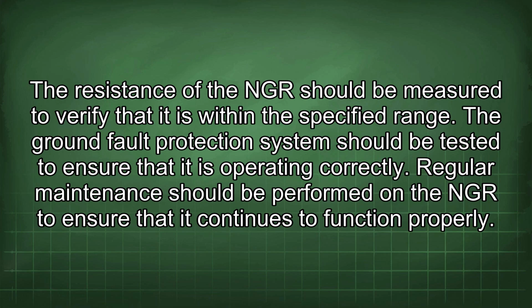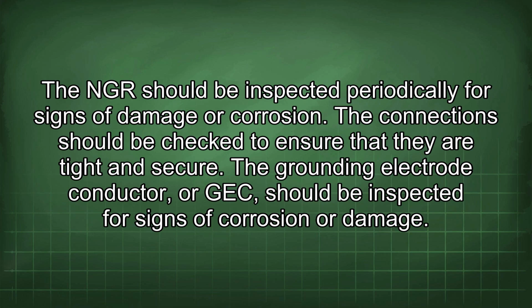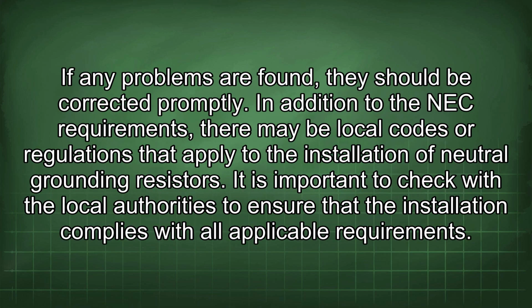Regular maintenance should be performed on the NGR to ensure that it continues to function properly. The NGR should be inspected periodically for signs of damage or corrosion. The connections should be checked to ensure that they are tight and secure. The grounding electrode conductor, or GEC, should be inspected for signs of corrosion or damage. If any problems are found, they should be corrected promptly. In addition to the NEC requirements, there may be local codes or regulations that apply to the installation of neutral grounding resistors.